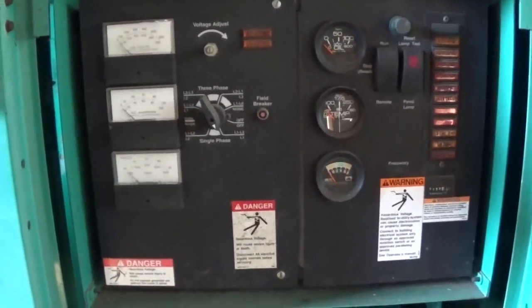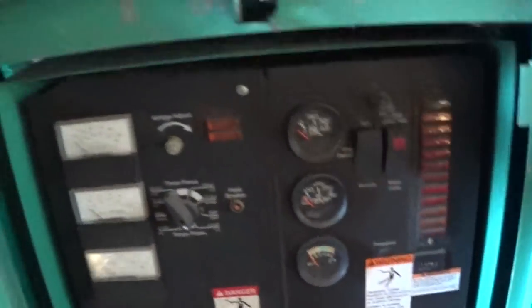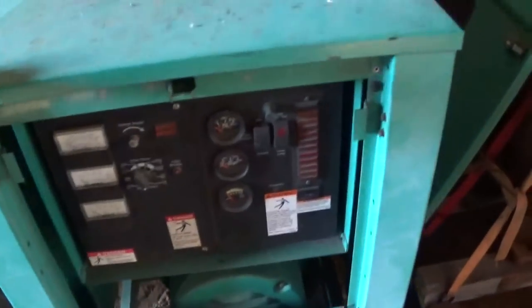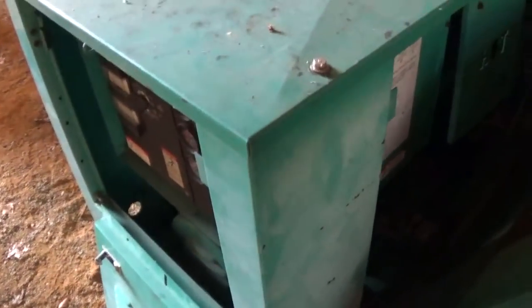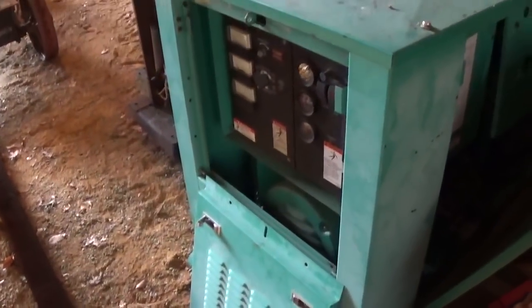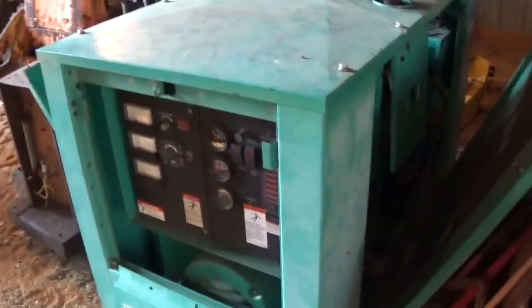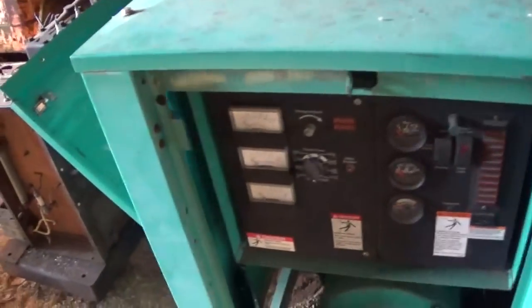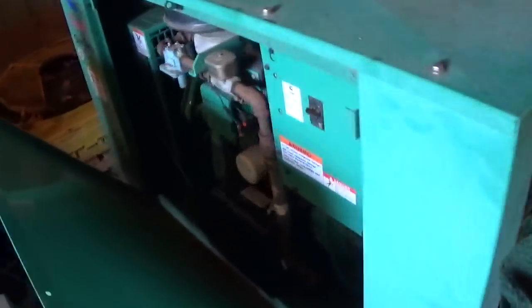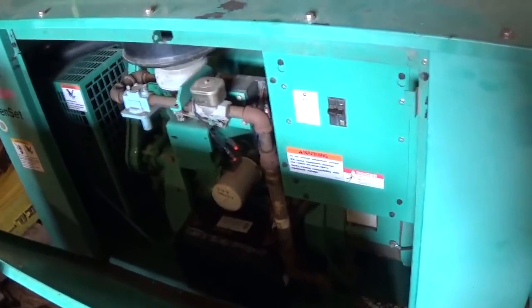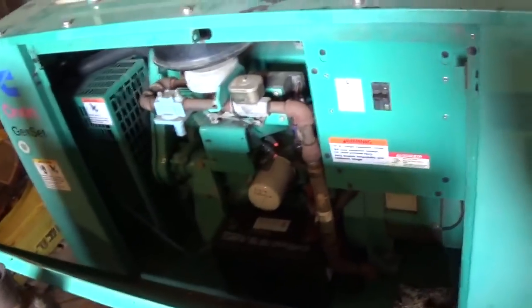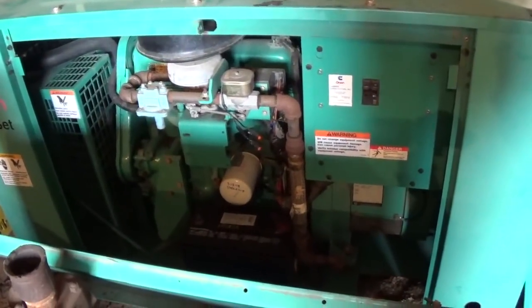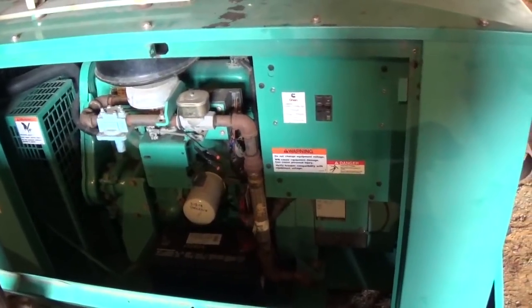The previous installation for this unit was at a security monitoring company. You're probably not going to be able to see anything in here. One thing they were fond of doing when inclement weather was forecast for the weekend was start the genset up and just leave it running, so that in the event of a utility failure, the ATS would swing right to generator with very little delay. The gen was already running, warmed up, and ready to accept the load. That's one of the main reasons why it's logged so many hours.